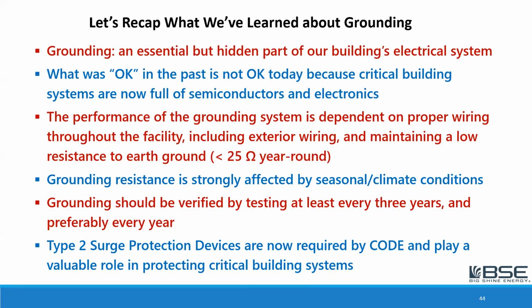And also for safety. If we have an unsafe system, that's a terrible situation, and we don't want that to persist. The performance of the grounding system is really dependent on proper wiring and connections throughout the facility, and especially the exterior wiring, because so many things were allowed in the past that weren't good, and maintaining a low resistance to earth ground, meaning less than 25 ohms year round. And we'd really like to see that be less than 5 ohms.